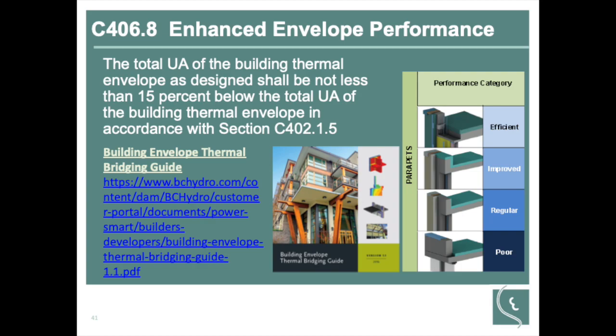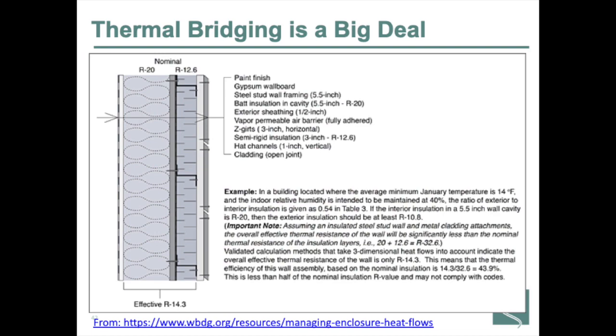One of the biggest things they focus on is thermal bridging. Thermal bridging can be real problematic, particularly in commercial, where we have metal building members and concrete, two materials that are really not very good insulators. And so here we've got a typical building wall section, and you can see I've got R12 on the outside of the building with some Z channel, and then an R20 back inside. But I have metal framing members. And so up here you say, okay, I've got an R32, almost 33 in there. But once I take into account the metal framing members, it's actually only an R14.3.